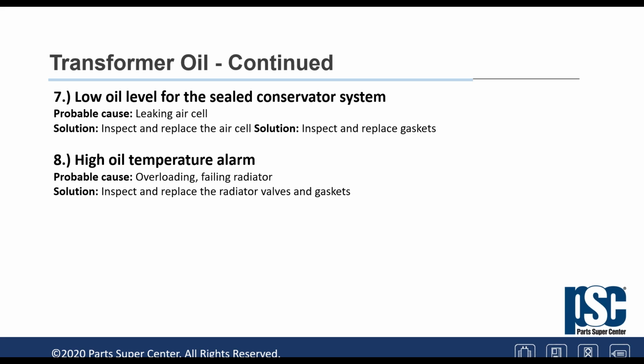Oil temperature alarm. Again, what tells the gauge to go up is the high temperature of the windings, which heats up the oil, and that's how the temperature goes up. Usually an oil temperature on a large power transformer is measured from 0 to 120 degrees C. For the winding temperature indicator, usually 0 to 160 degrees C. So by looking at the gauge, we know if it's a winding temperature or oil temperature indicator.